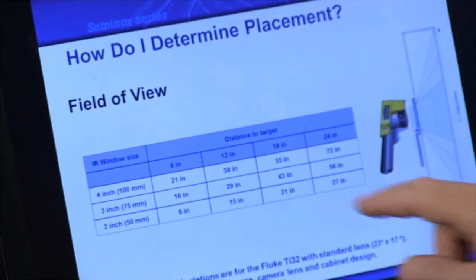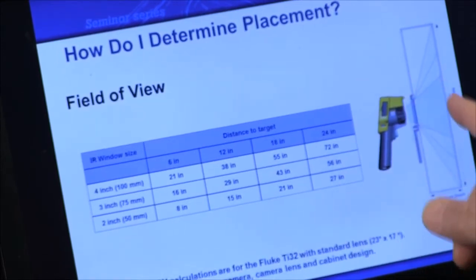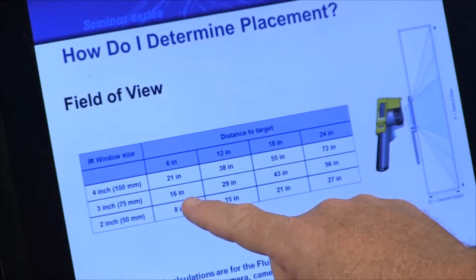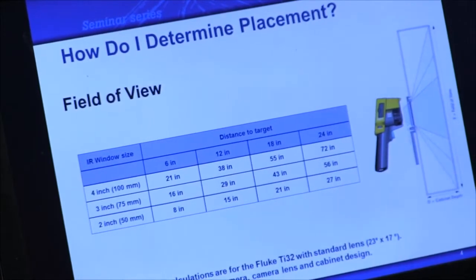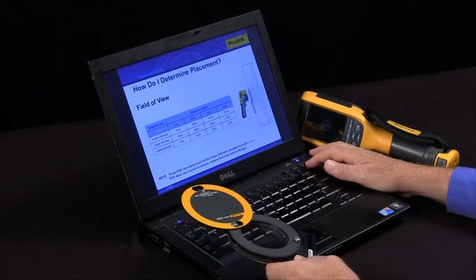So for example, a six inch. If it's six inches from the front of the cabinet to where your target is, then with a three inch window you'll be able to see 16 inches from top to bottom or side to side. If you have 12 inches you can now get 29 inches, and there's a great field of view calculator on the Fluke website that can help you as well.